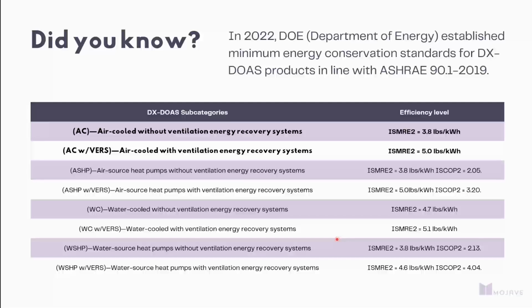minimums. And what it's looking at is how much moisture can you remove, or how much water can you remove from the air per kilowatt hour of input. So how much water can you remove from the air for each unit of energy input. Similarly, this is like IER for DOAS. It is a simple conceptual parallel. So IER is how many BTUs can you remove per kilowatt hour. ISMRE is how much water you can remove per kilowatt hour. And this is in ASHRAE 90.1 2019, as well as IECC 2021 and beyond.